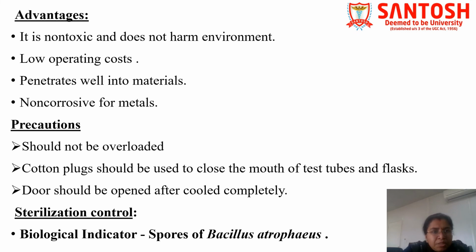Okay. So the advantages: it is non-toxic and does not harm the environment, it has very low operating cost, it penetrates well into the materials, and it is non-corrosive. But the precautions are, again, it should not be overloaded, cotton plugs should be used to close the mouth of test tubes and flasks, and the door should be opened only after some time when the hot air oven gets cooled. The biological indicator for this process is spores of Bacillus atrophaeus.